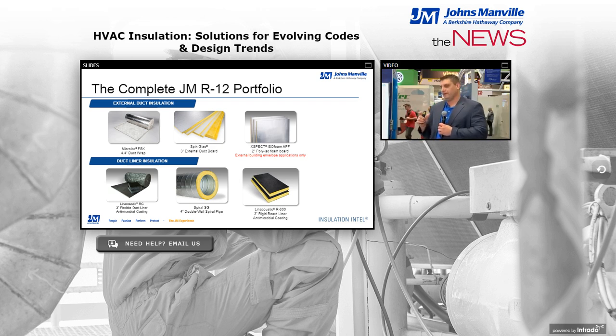The polyiso products get a very, very good R value per inch. What's interesting about our Xspect foam product is you really have to be careful where you apply the product. Our insulation requirements are very strict on our flame and smoke spread rating, the ASTM E84 test. We are required to meet a 25/50 flame and smoke spread rating for duct work in all duct applications. The polyiso product has no issues making the 25 on the flame side, but it has issues with the smoke spread index. So it's got to be on the outside of the building. It's got to be used out there.